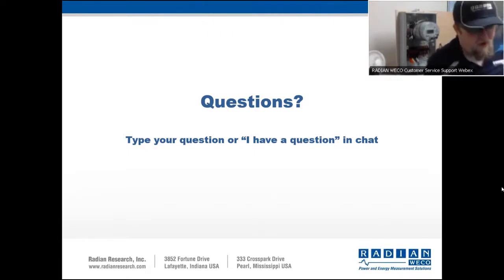Next question, do all RWs have the built-in dead site test option, or is that something that has to be added in as an option? It is an accessory for the RW, so you will need a CT current boost accessory to perform dead site tests, to give that 200 amp boost that I keep talking about. It is a standalone accessory, comes in a little box that you can then use to power primaries of CTs to either bench test or boost a low load or no load application out there.